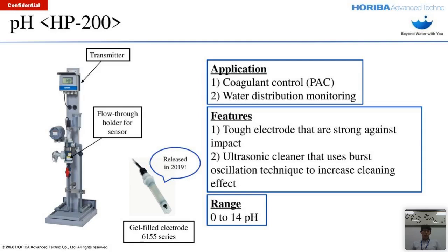For the first parameter that I'd like to introduce, pH, we have the HP200 series. Some of its features include a tough electrode, where the glass of the electrode is reinforced to better withstand impact. This is very useful in preventing breakages for processes where insoluble metals are present in the water along with a high flow rate. For feature number two, we have an ultrasonic cleaner that uses a burst oscillation technique to increase the cleaning effect as compared with our conventional ultrasonic cleaners.